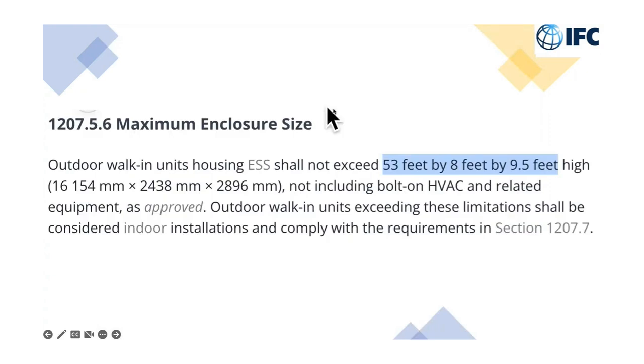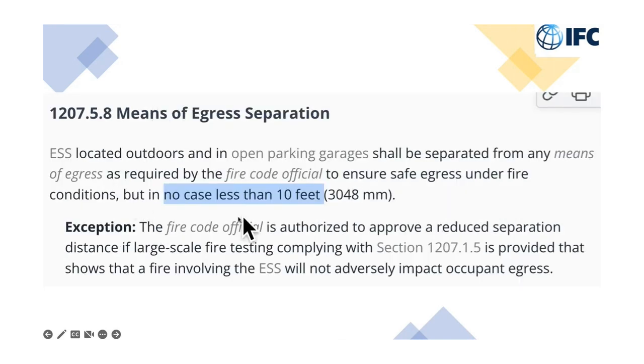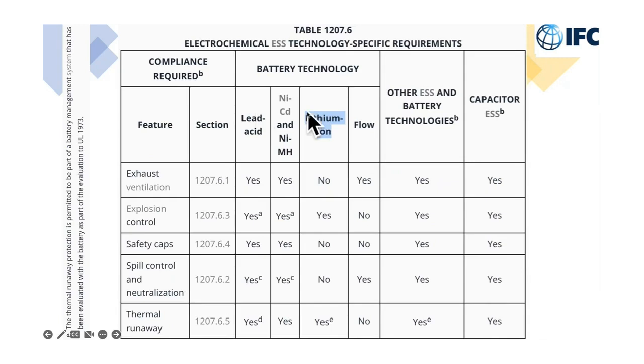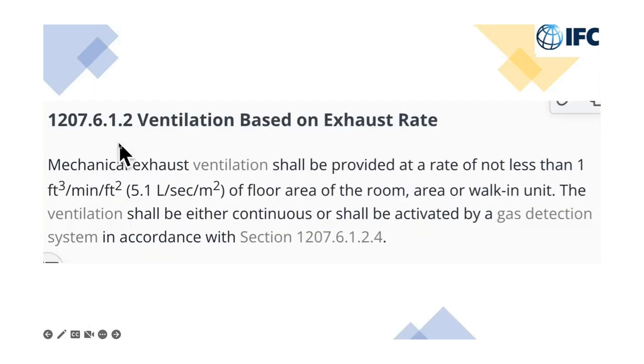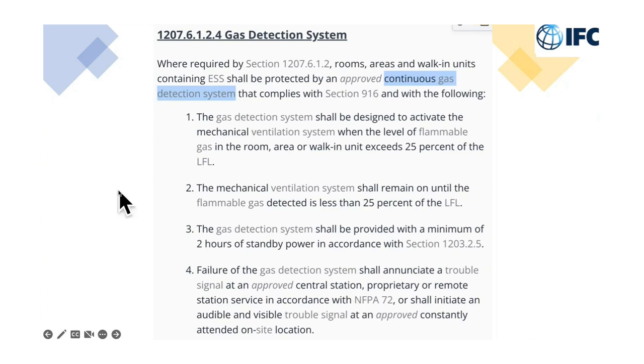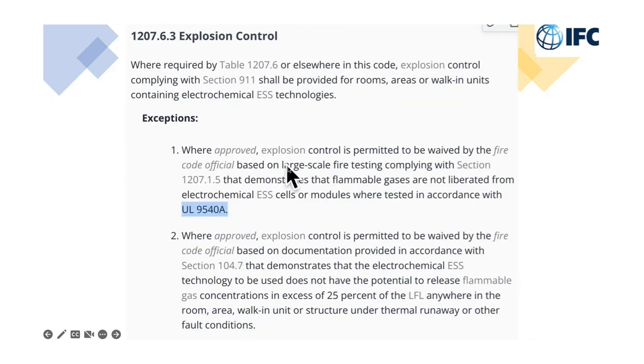Maximum enclosure size. I believe this would be like a container, 53 by 8 by 9.5 feet. Sounds like a real long container, or maybe a container with some things attached to it. And separation, no less than 10 feet, but we can overrule that with a fire code official. 10 feet sounds like a good number to me. And so we could see, just for lithium ion, explosion control, thermal runaway, and a lot of this stuff too is going to be done with the 9540A fire testing, exhaust ventilation, talking about gas detection. Some of this stuff, I think, there it is, 9540A again, has a lot to do with these big giant utility scale energy storage systems.